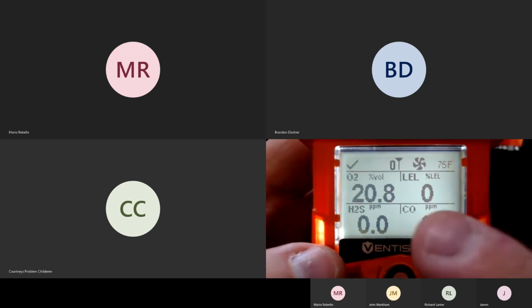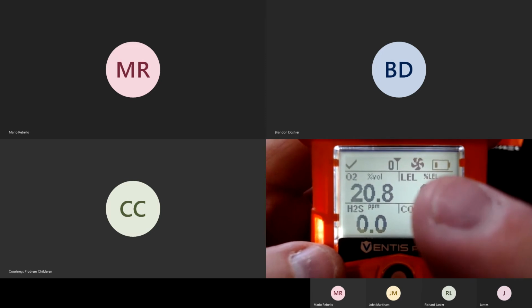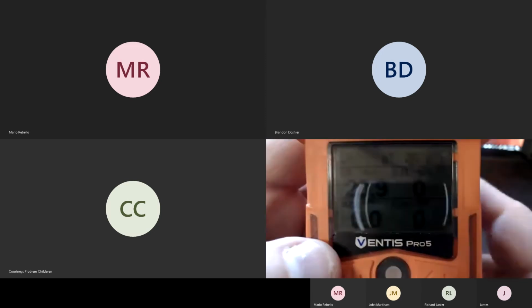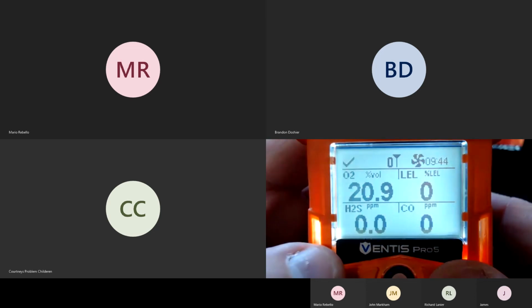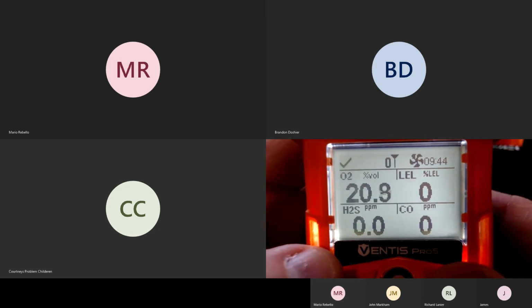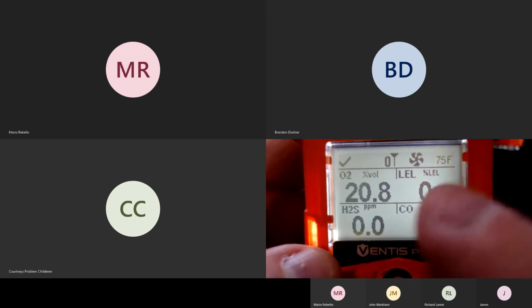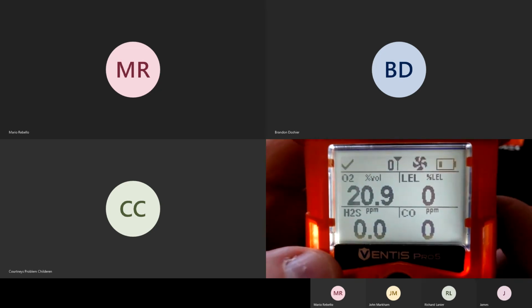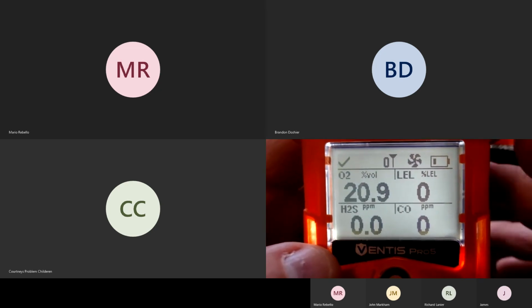Up here at the top, you see the little fan. That's telling me that I have a pump and that it's running. Next to it, I've got the little antenna with the number 0 next to it. That's that wireless. It's telling me right now I don't have anybody connected to me. And then in the top left-hand corner, I have a check mark. The check mark means that it is checking for gas.